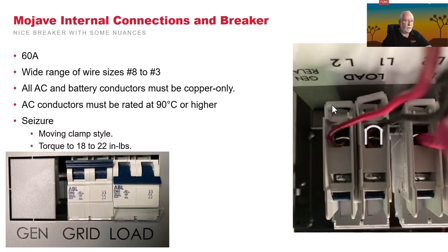Now, a couple of extra things that are outside of that video. First of all, our breakers will handle 60 amps. That's what they're rated. You can see it on the front. There's a wide range of wire sizes that it'll handle, from number 8 to number 3. All of the AC conductors must be copper. All of the AC conductors must be rated for 90 degrees C or higher if they're inside the cabinet.